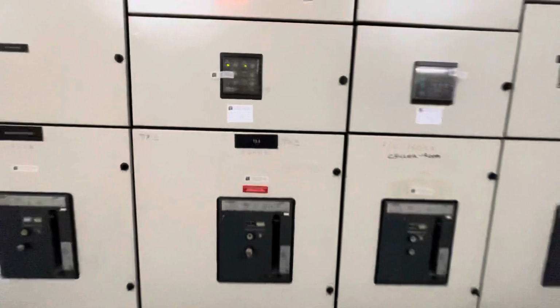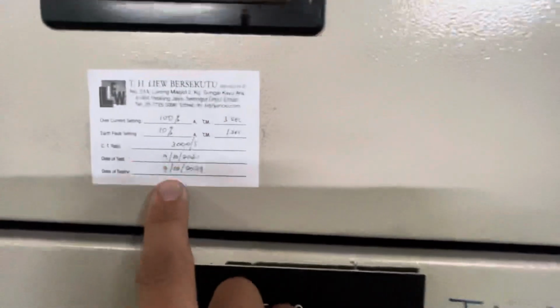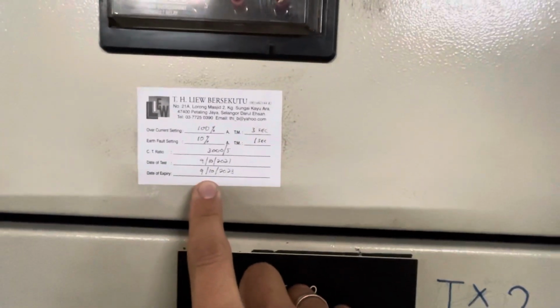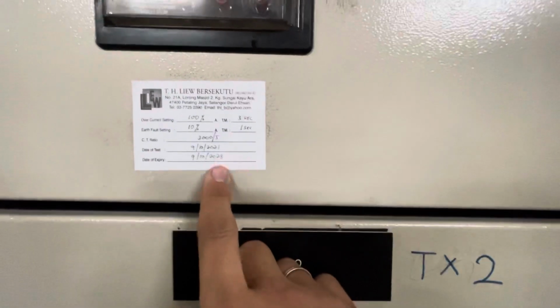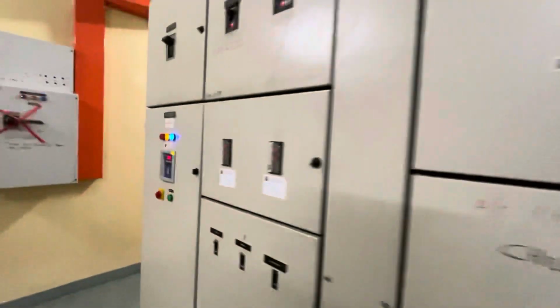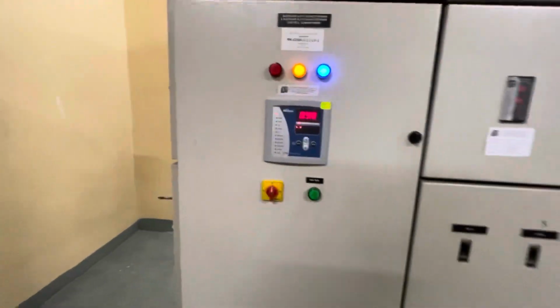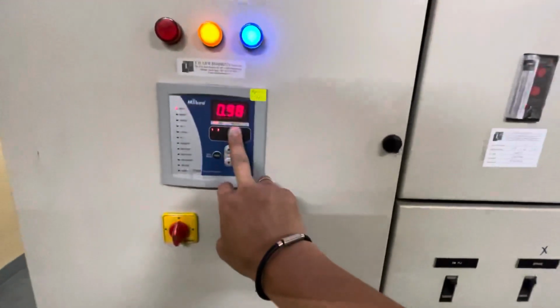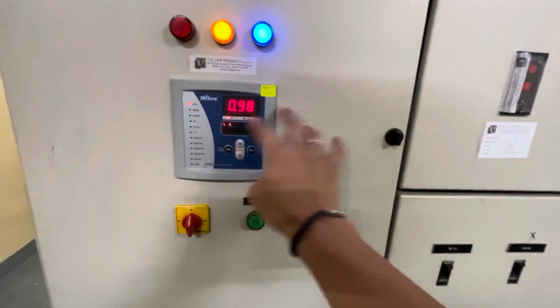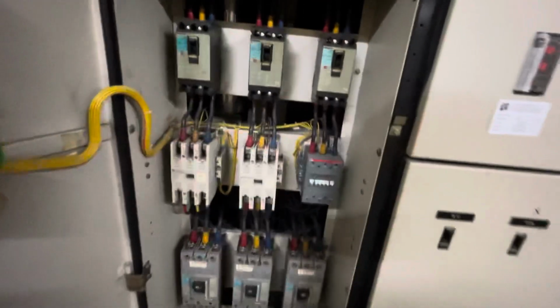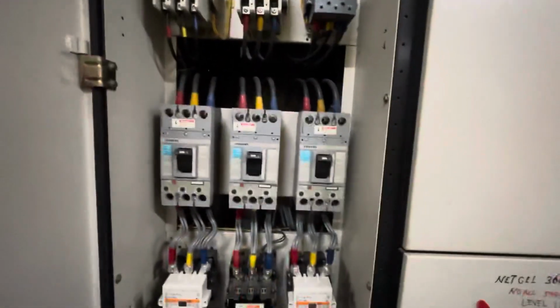Okay, let's check the calibration. Calibration expiry is on the 9th October 2023. Still long to go. Let's check the incomer number 1, MSB number 1, power factor. Power factor currently is at 0.98, step 1 and 2 on. Let's check inside. We have a contactor humming.